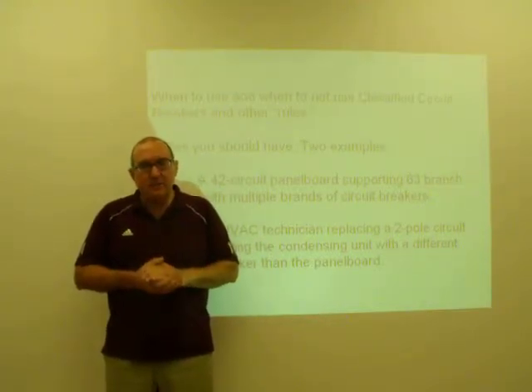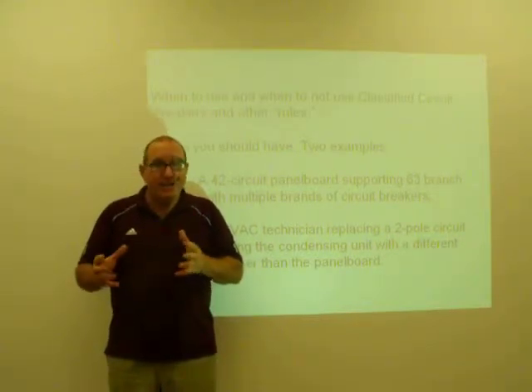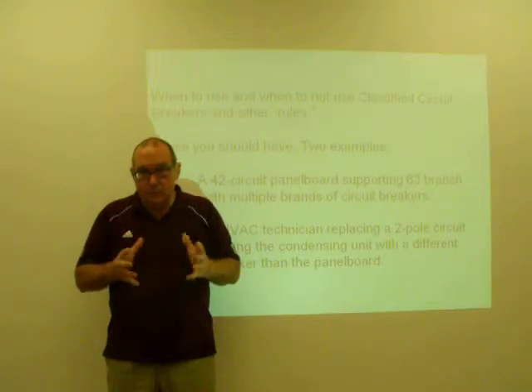The second example is more recent. An HVAC technician replaced a 2-pole circuit breaker in the home of a friend. The breaker apparently had suffered some sort of failure. The air conditioner quit working, and an air conditioning mechanic came out and repaired it. In the process, he installed a different brand of breaker in the panel board than what was the brand required.